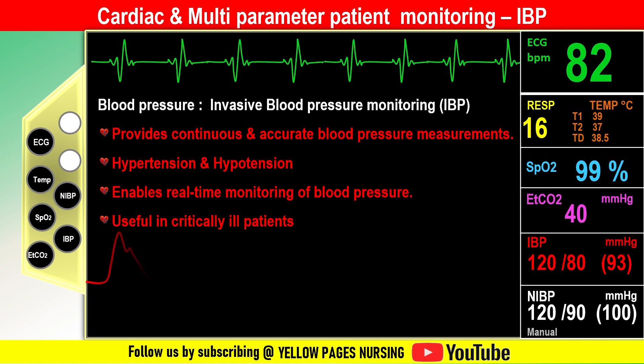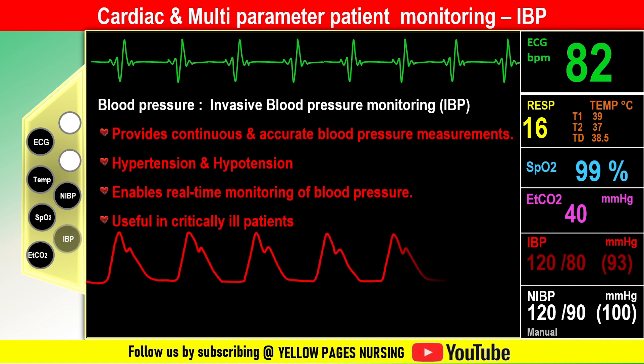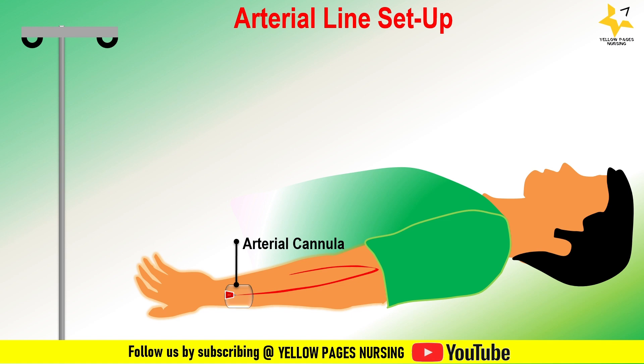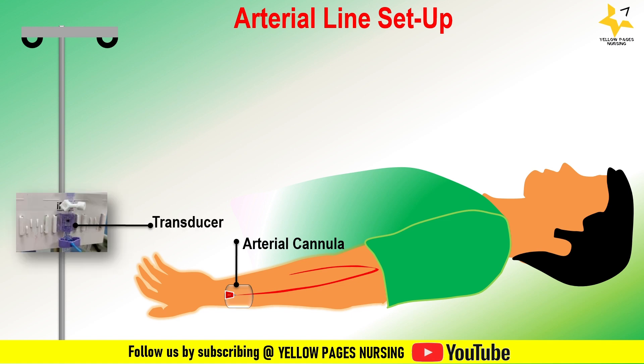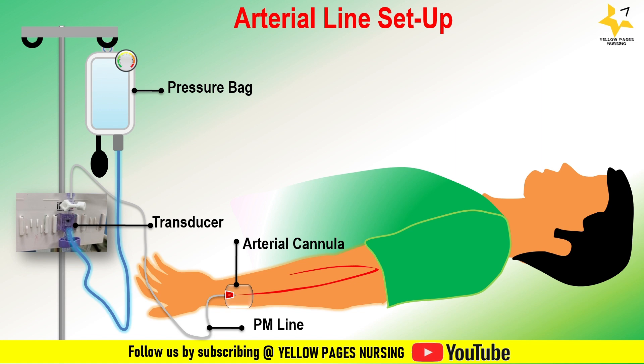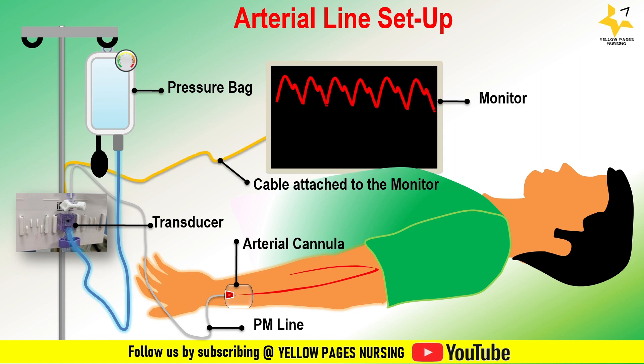Invasive blood pressure monitoring uses an arterial line setup. An arterial catheter is inserted into the radial artery. A transducer is connected on the IV stand at the level of the phlebostatic axis. A pressure monitoring line is connected to the transducer kit, a pressurized saline bag is attached to the IV pole, and IV tubing connects to the other end. A cable from the transducer is attached to the monitor for measuring real-time blood pressure. Nursing considerations: remove air and clots from the lines and check backflow of the arterial line.